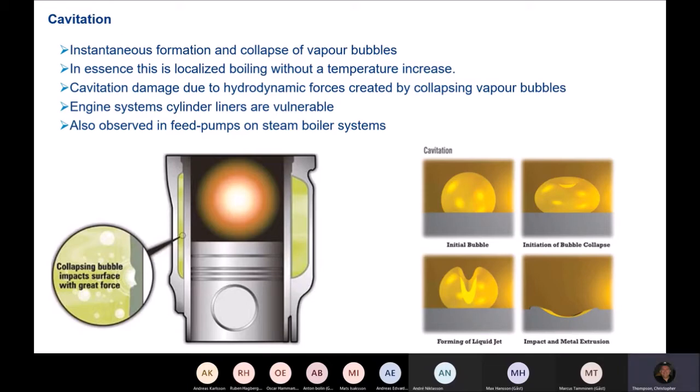So they've actually decided, MAN, across the range to increase the nitrites in the engine water cooling chemical, double the chemical quantity, and that is actually putting the magnetite layer thicker where the cavitation is having a problem. So they've engineered the problem out by putting more chemicals in there to stop the engine damage. So if you go on board a vessel with MAN engines, the recommendation for the nitrite should be 1,000 to 1,500. They're now saying 2,500 to 3,600 to get around the problem of the engineering mistake.